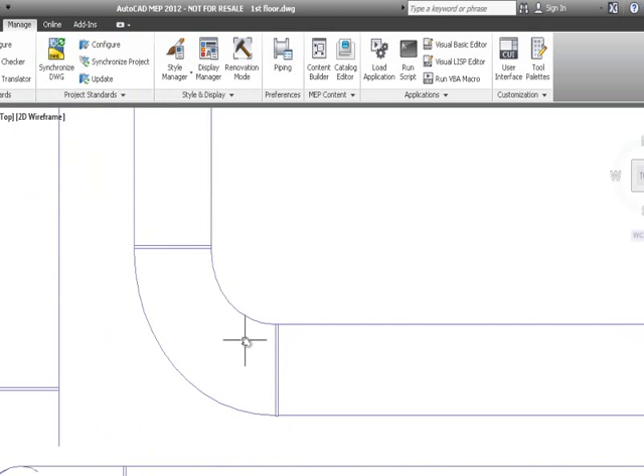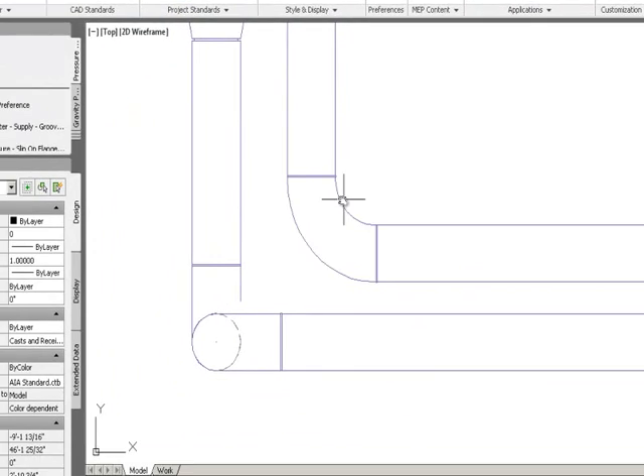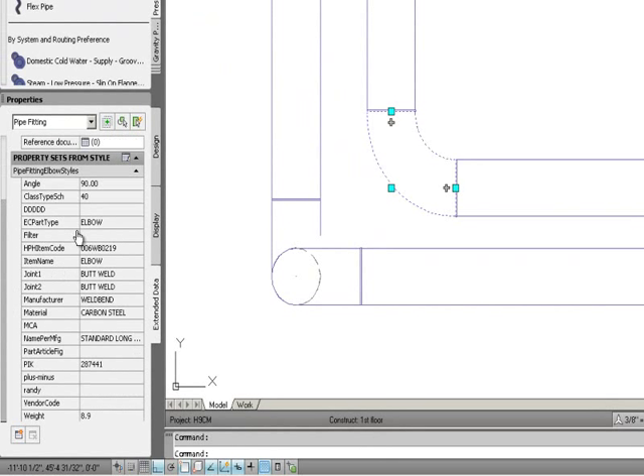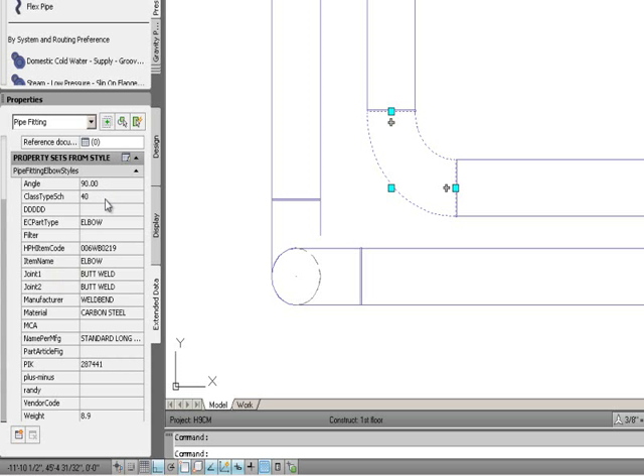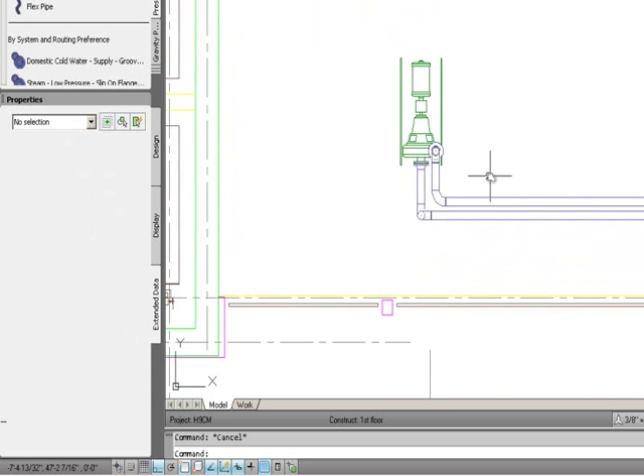Now you'll notice there's a weld gap between the elbow and the piece of pipe, so I'll get an exact cut length on the pipe that's precise to what I need. When I click on this elbow and look at the extended data tab, you'll see all the data filled out — even the HPH item code and the weight of the elbow at 8.9 pounds, because that's my weld-bend 90-degree elbow schedule 40. That was taking generic content and switching it over to manufacturer's content.